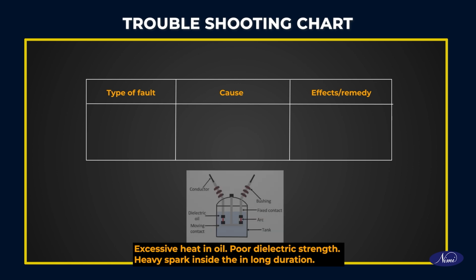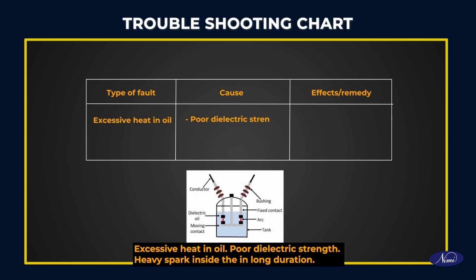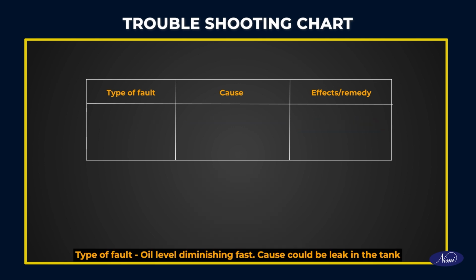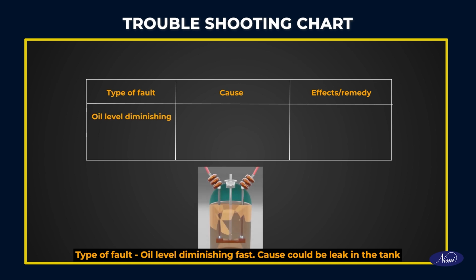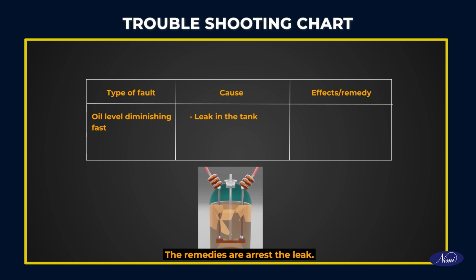Troubleshooting chart. Excessive heat in oil. Poor dielectric strength. Heavy spark inside the tank in long duration. Type of fault: oil level diminishing fast. Cause could be leak in the tank. The remedy is to arrest the leak.